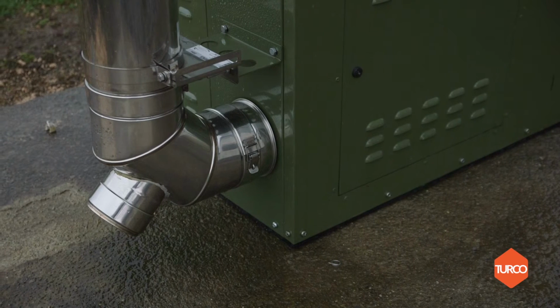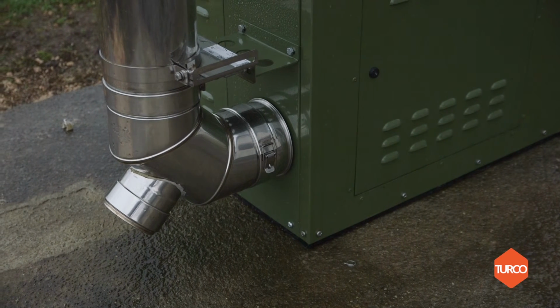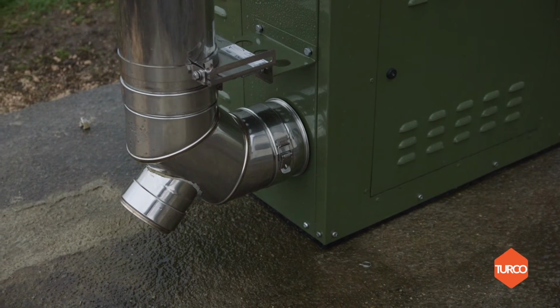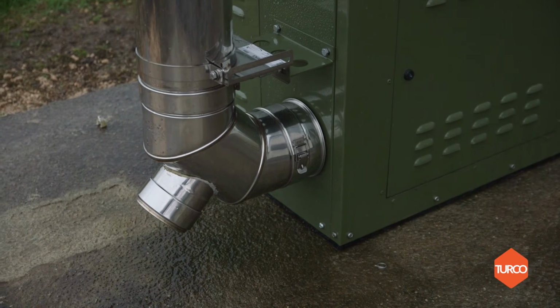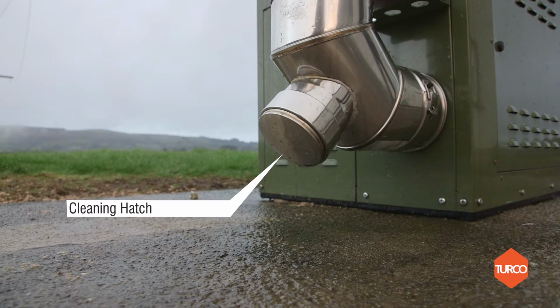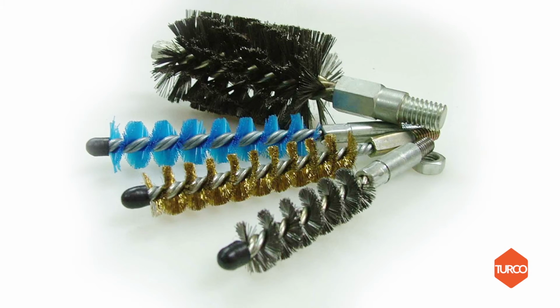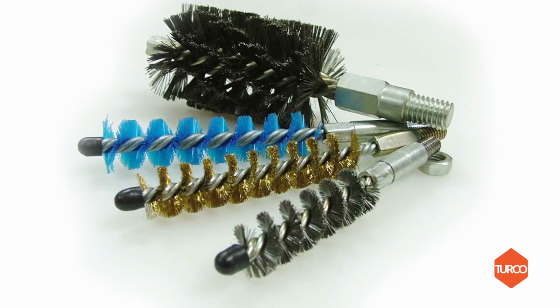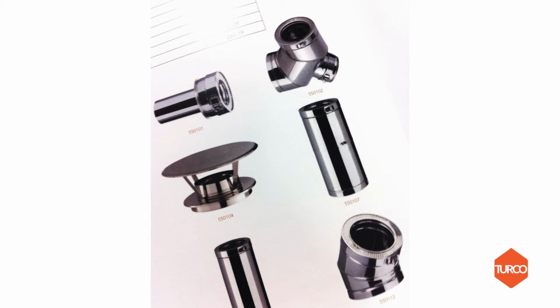It is important there are no 90-degree bends used on the flue system apart from the 90-degree elbow at the rear of the 28kW boiler. A cleaning hatch or way of removing a piece of flue to enable annual cleaning of the flue needs to be provided at any 90-degree bend. A full range of straight, offset, elbow and T elements are available from Turco.